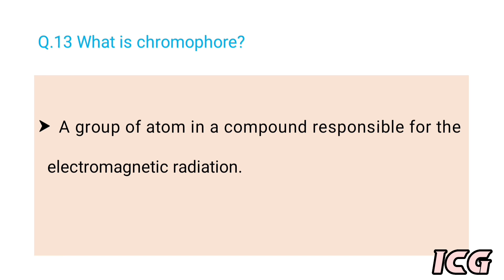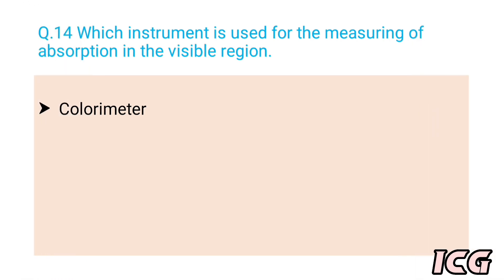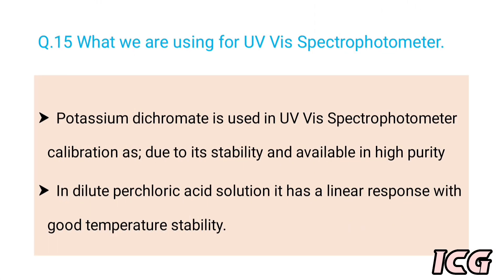The next question is: what is a chromophore? The answer is a group of atoms in a compound responsible for the absorption of electromagnetic radiation. The next question is: what instrument is used for measuring absorption in the visible region? The answer is a colorimeter. The next question is: what is used for UV-Visible spectrophotometer calibration? The answer is potassium dichromate, because of its stability, high purity availability in dilute perchloric acid solution, and linear response with good temperature stability.